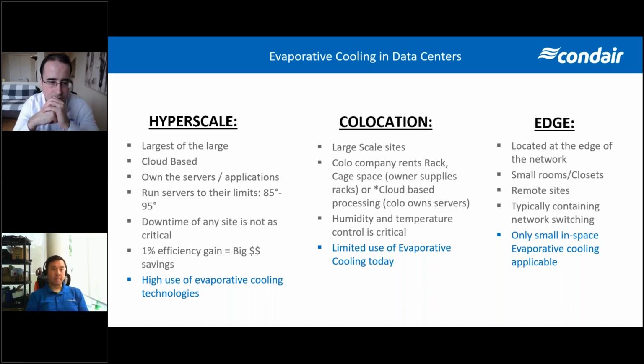Nuno talked about the amount of energy that's required here. And then we'll talk about the water consumption as well on some of these adiabatic systems. But because of the scale of these types of systems, even a 1% efficiency gain on the cooling side can make a really big difference in overall operating costs for these facilities. Even though a lot of that power is still required for the computing, we can certainly help improve efficiencies on the cooling side as well. So that's on the hyperscale side.